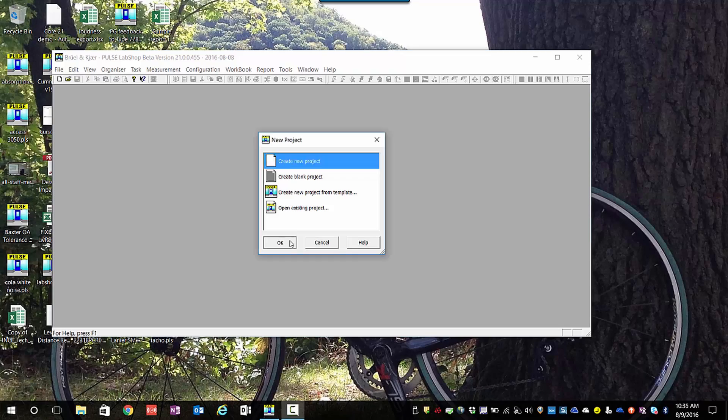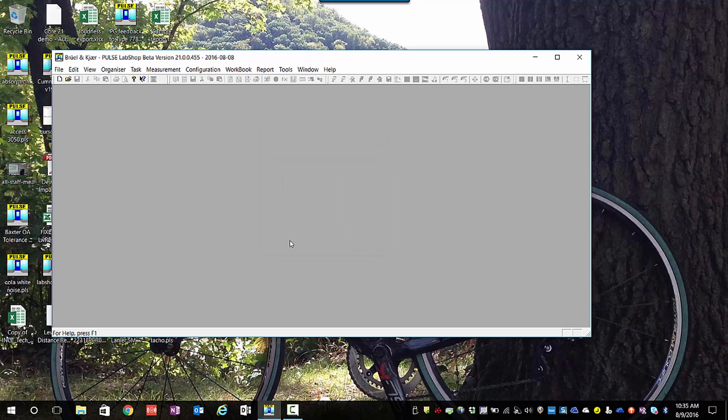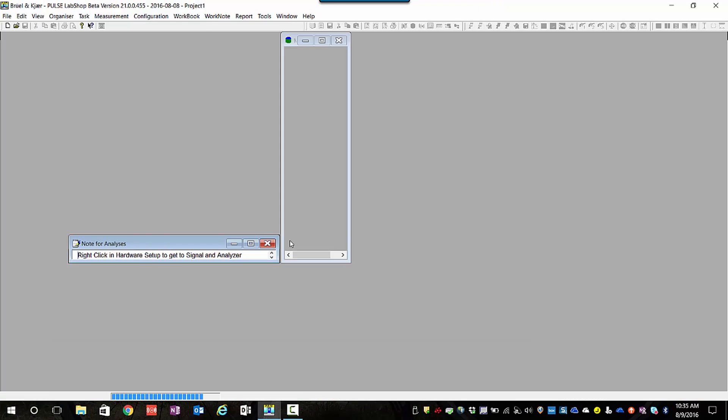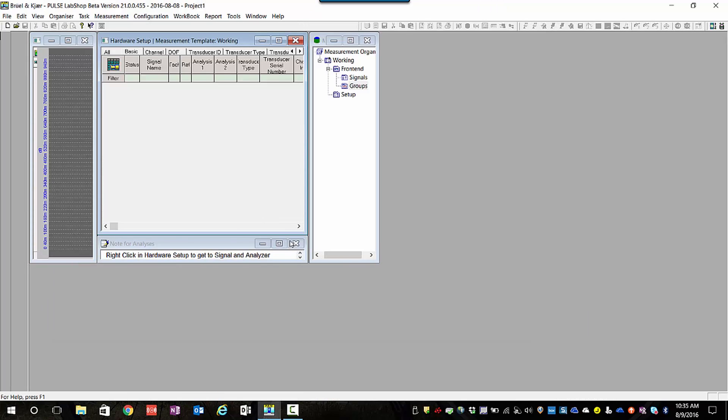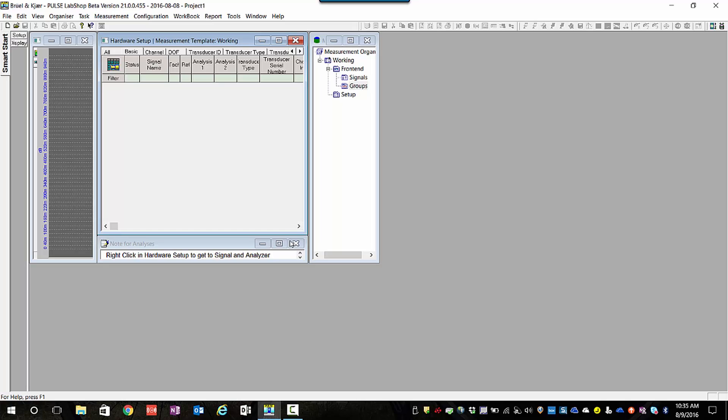So here we are opening a Pulse Lab Shop project. When you initially open the project that connects with the data acquisition hardware, I have connected a six-channel LAN-XI module with a triaxial accelerometer connected to the first three channels.